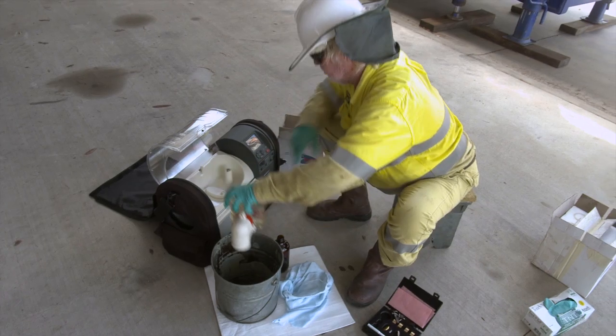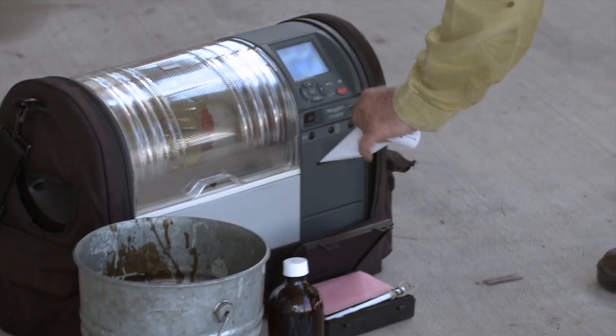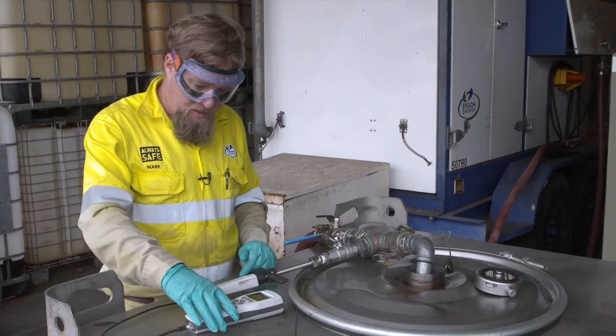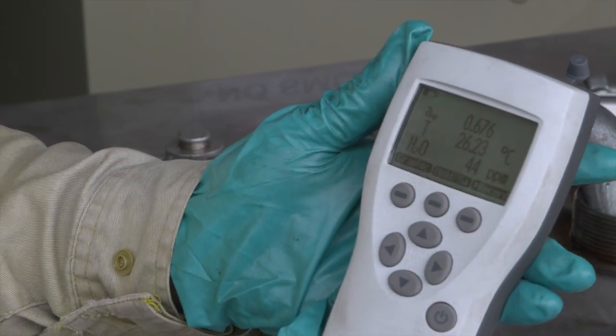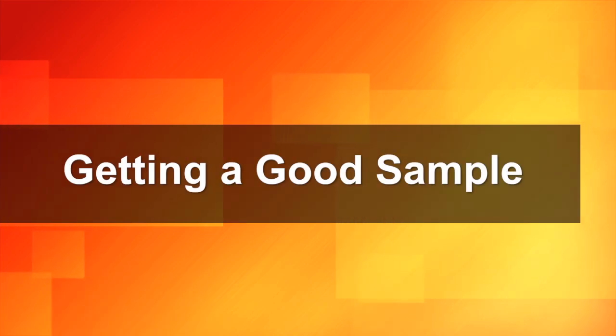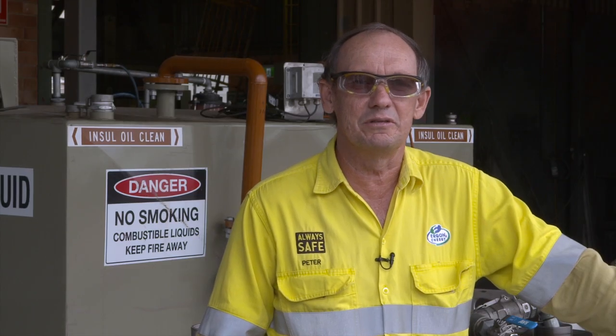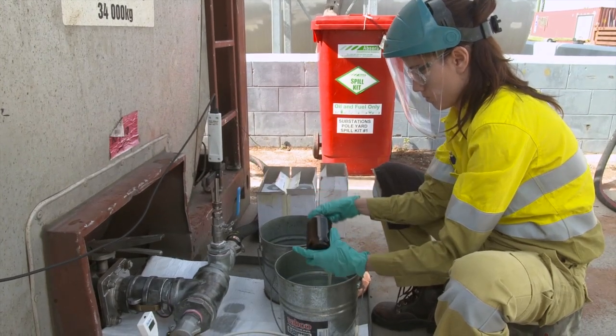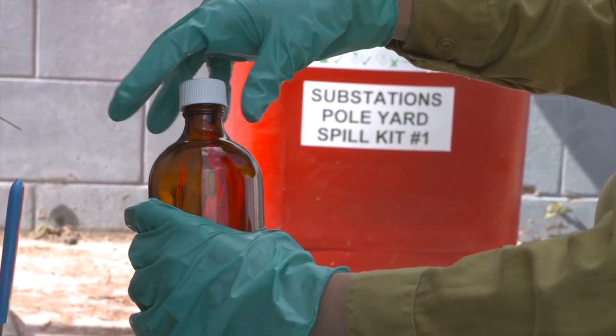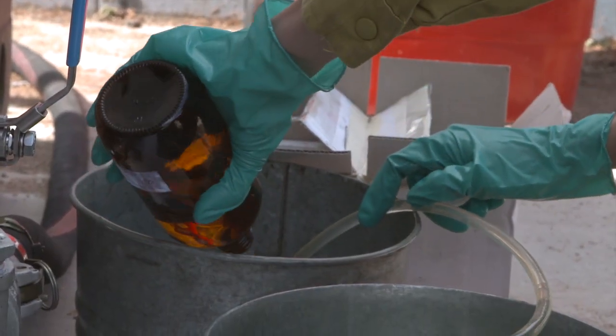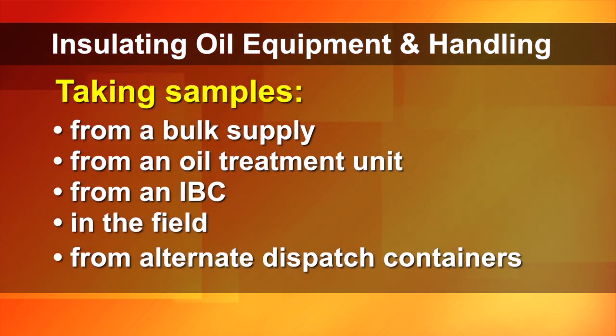Okay, when it comes to care and maintenance of equipment, cleanliness is the key, making sure that everything is always stored in a dry atmosphere. As part of this process, we require that all your test equipment be tested and calibrated on a 12-monthly basis. That applies to both the oil breakdown testers and the moisture monitors. Oil is so susceptible to contamination, mainly from moisture, so we've got to keep things clean. It's important that you flush your sample bottles with clean oil. When taking oil samples, there are just a few things to remember, depending on where you're taking your sample from.